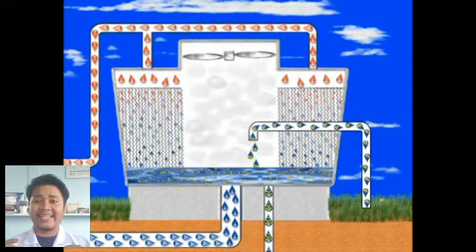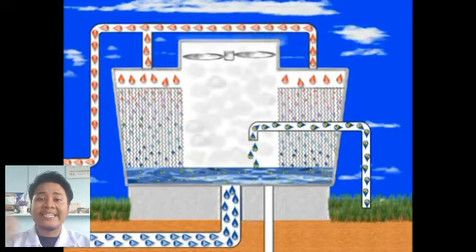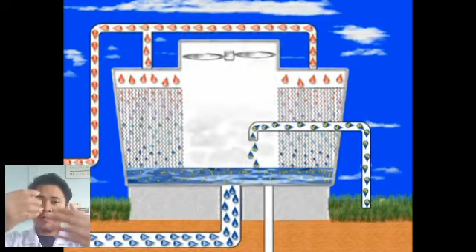Fresh water is introduced to the cooling tower through the makeup supply. It carries extra elements into the system water where they accumulate, because the more water that evaporates, the more makeup water is needed to replenish the system. In order to reduce the concentration of elements in the system, a bleed valve then opens and drains the wastewater discharge.